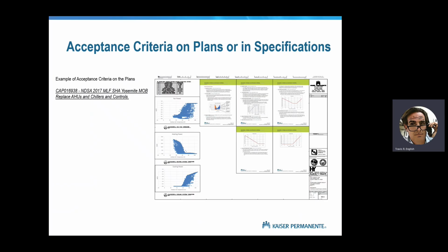You probably can't read this, but I hope you can see that these charts for fan power and heating power and cooling power are right there on the plans at different outside air temperatures to show what we expect to see. This gives our commissioning team what they need to go out there and validate these systems. And that, plus a good controls design, I should say.